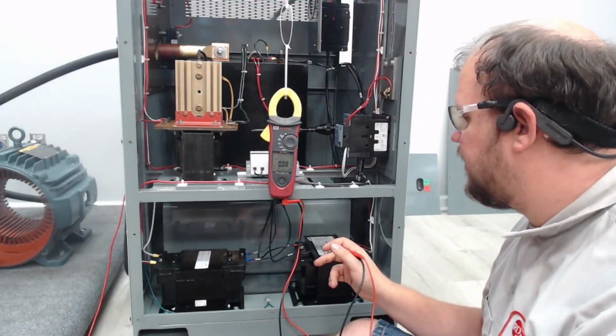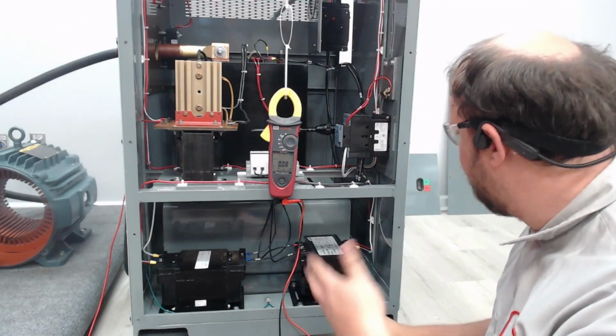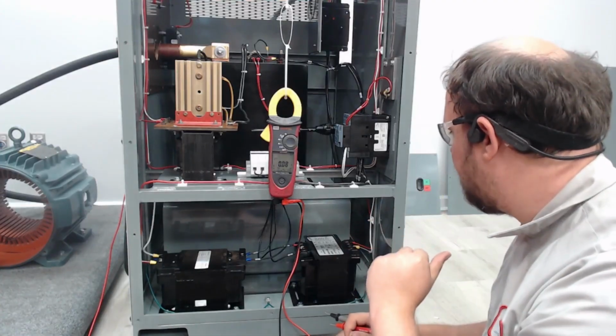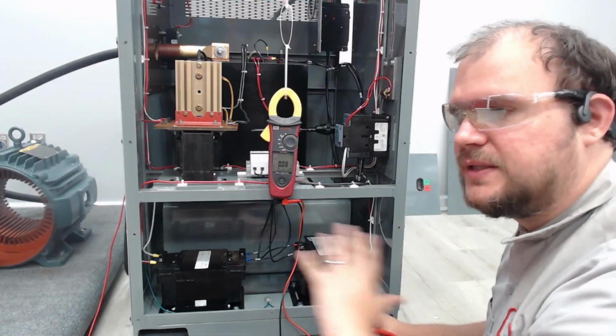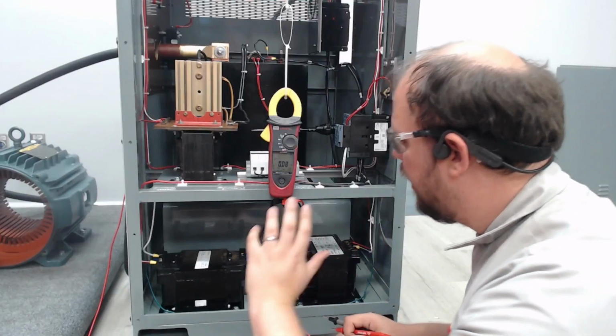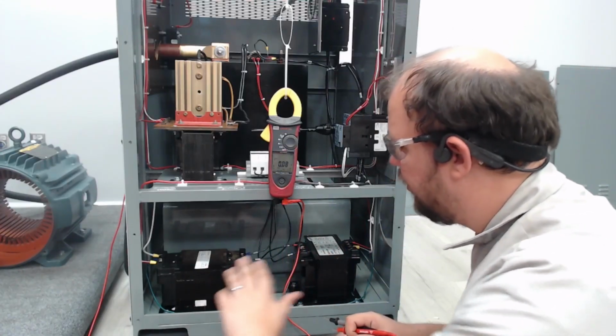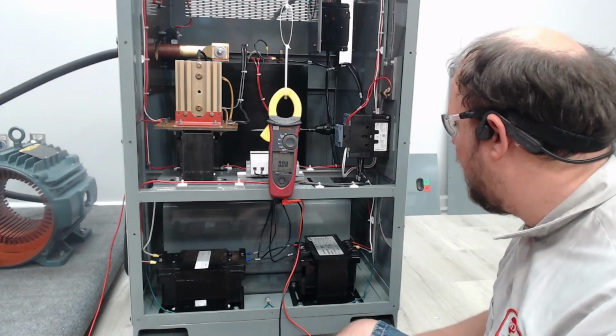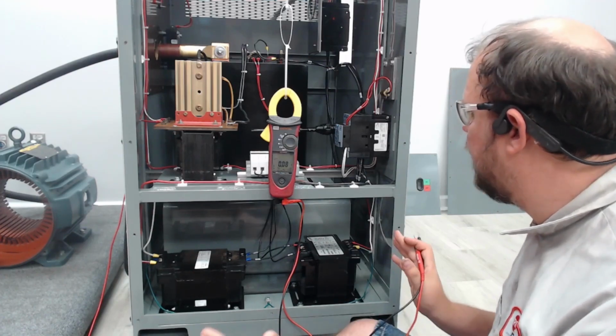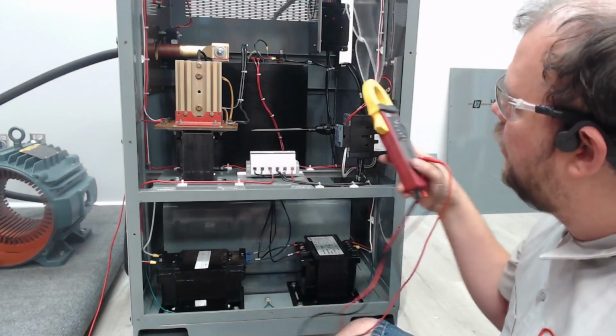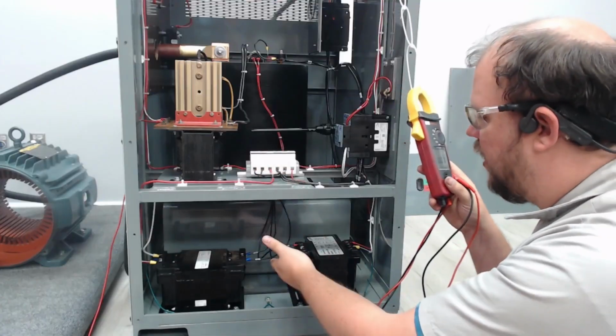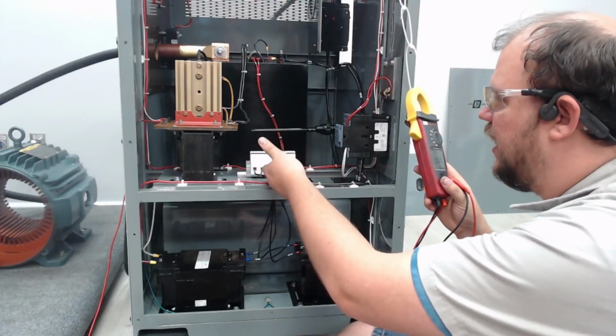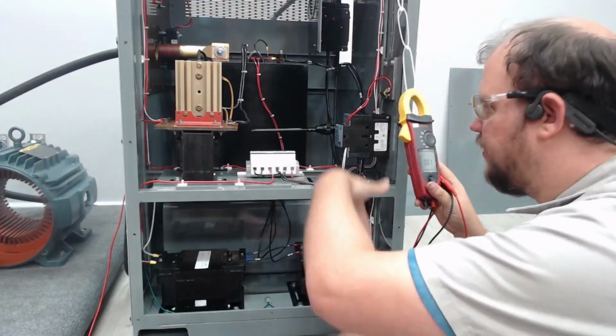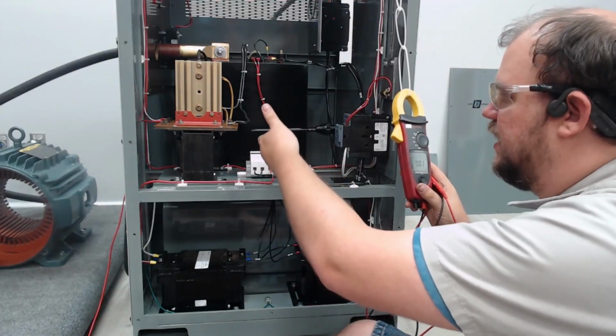So we got the 460 going in. We got the 120 out. We checked the wiring, the schematics. I'm not going over that. That needs to be your own understanding. But you read it and you make sure it's right, it's there. And then you're checking out for 120 going out. You can also check at the fuse blocks. Maybe you're not able to get to the meters, but you can still check using the schematic, trace the wiring, and check at the fuse block ends.